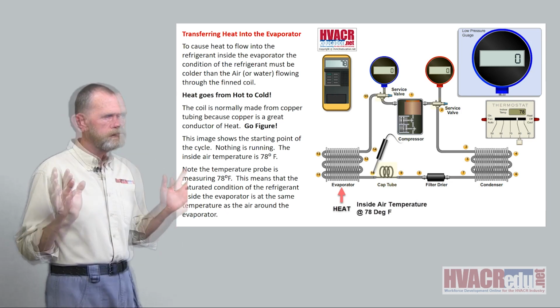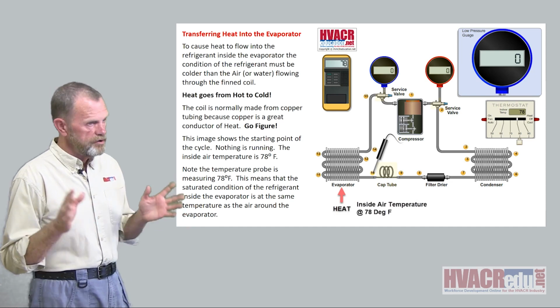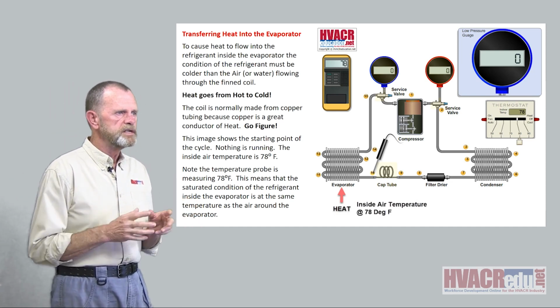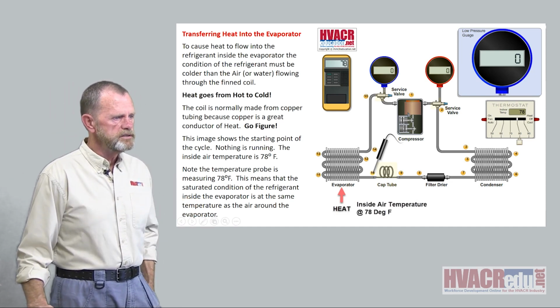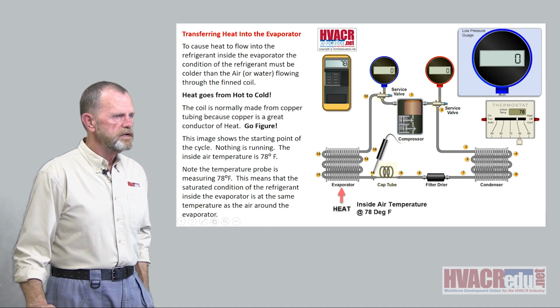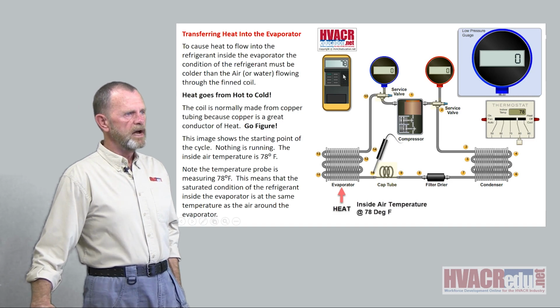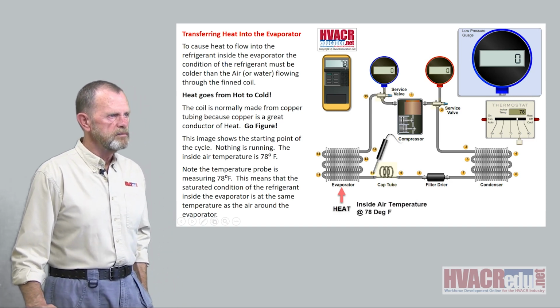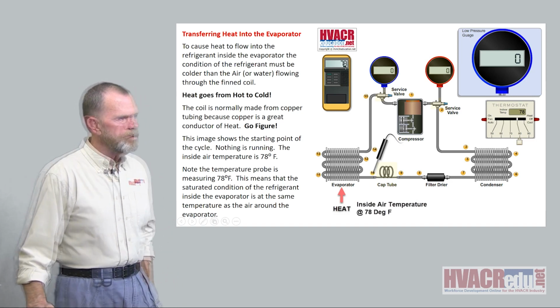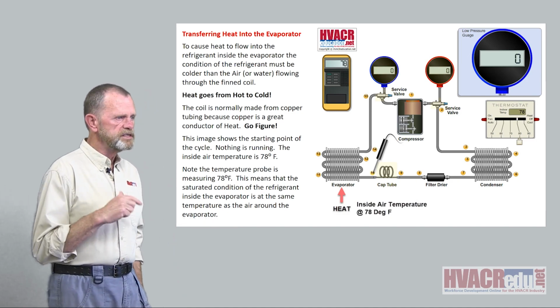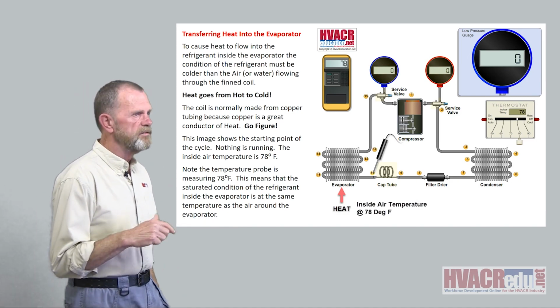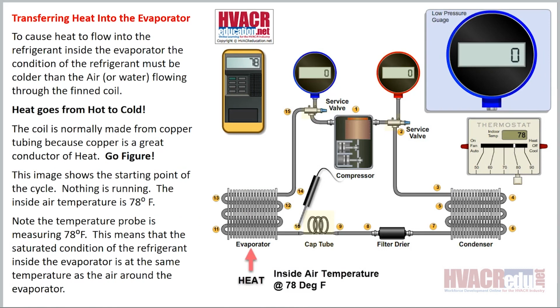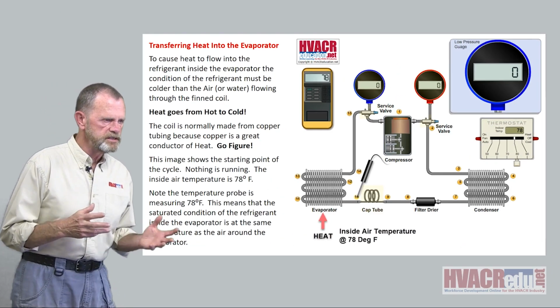Nothing is running. If that compressor is not running, nothing else is going to happen. The inside air temperature must be 78 degrees. And why do I say that? Because I've got the surface probe here on point number 10 at the inlet of the evaporator, and my thermometer is telling me it's 78 degrees. That means that the saturated condition of the refrigerant inside the evaporator is at the same temperature as the air around the evaporator. And before you start up a system, that's exactly true.